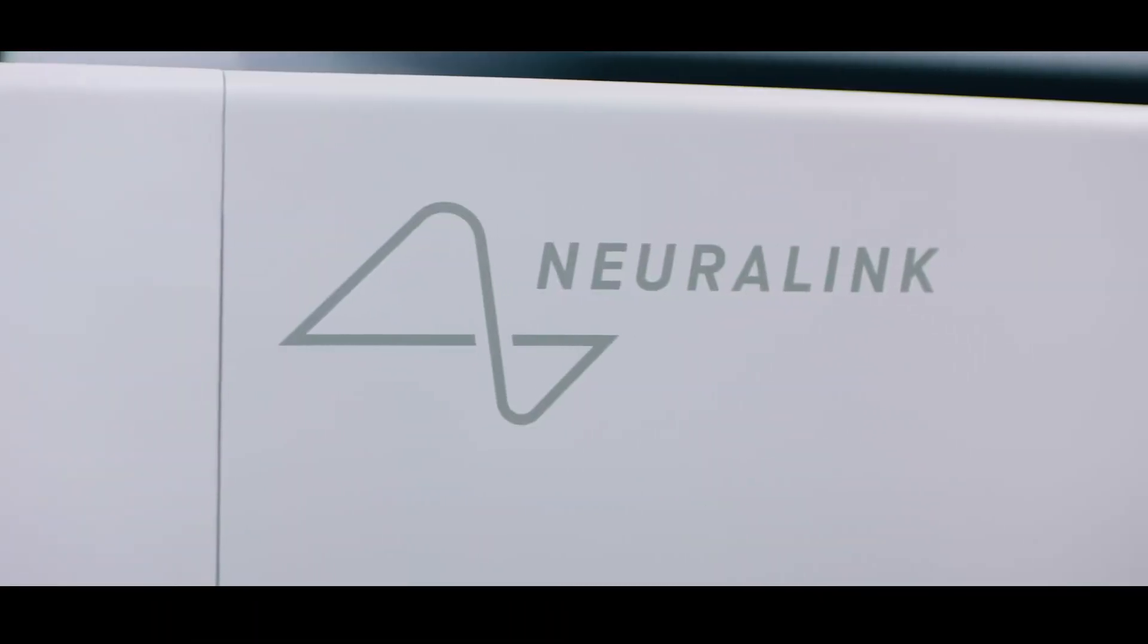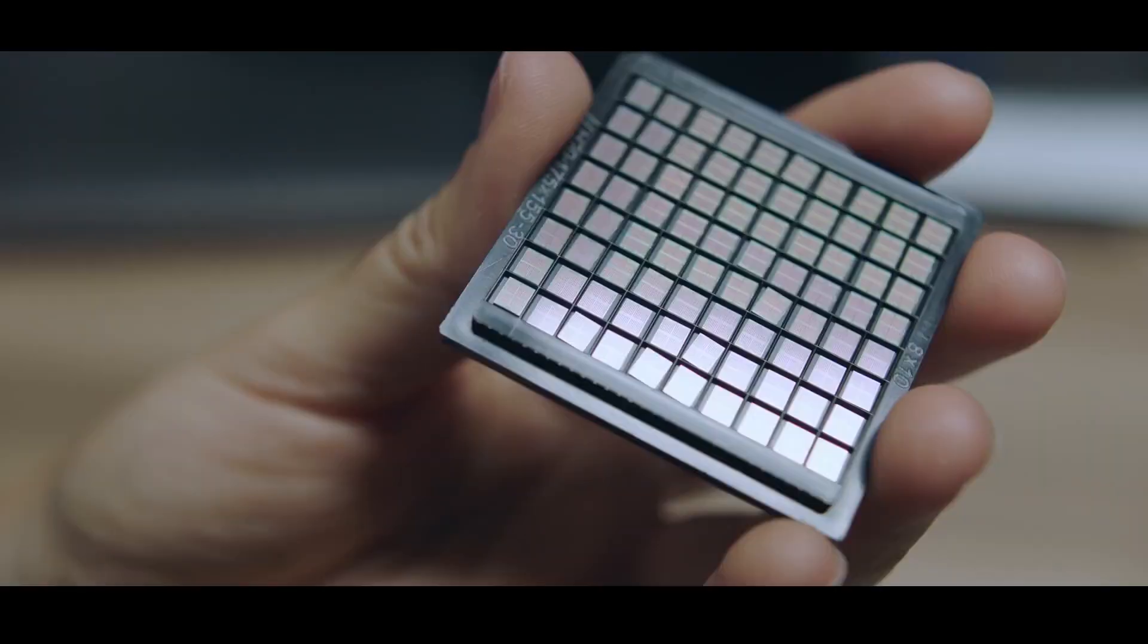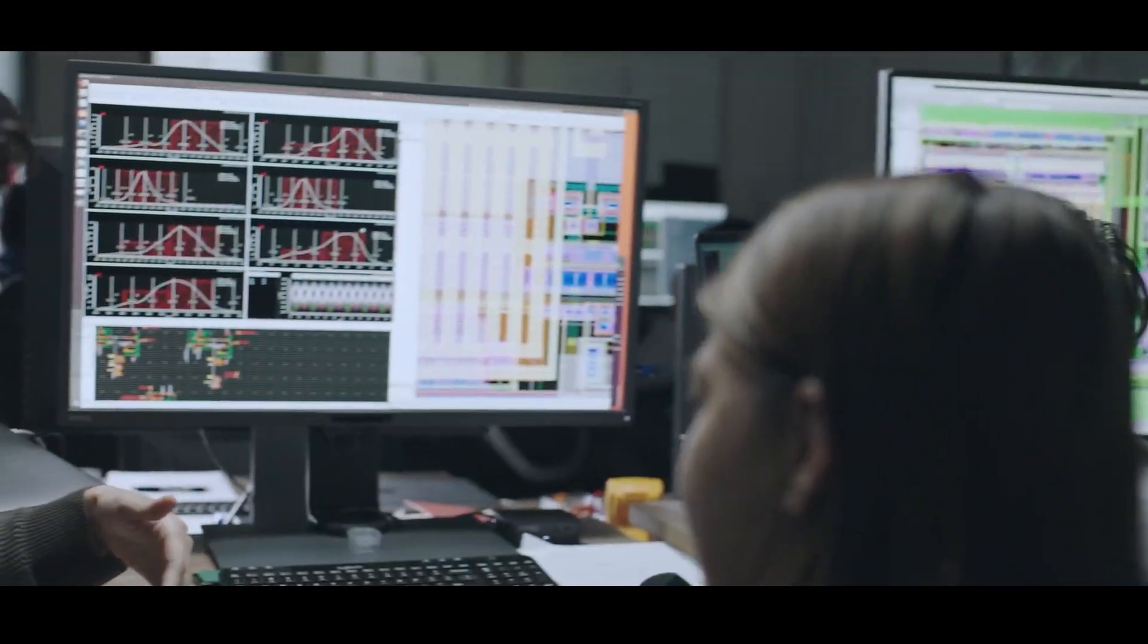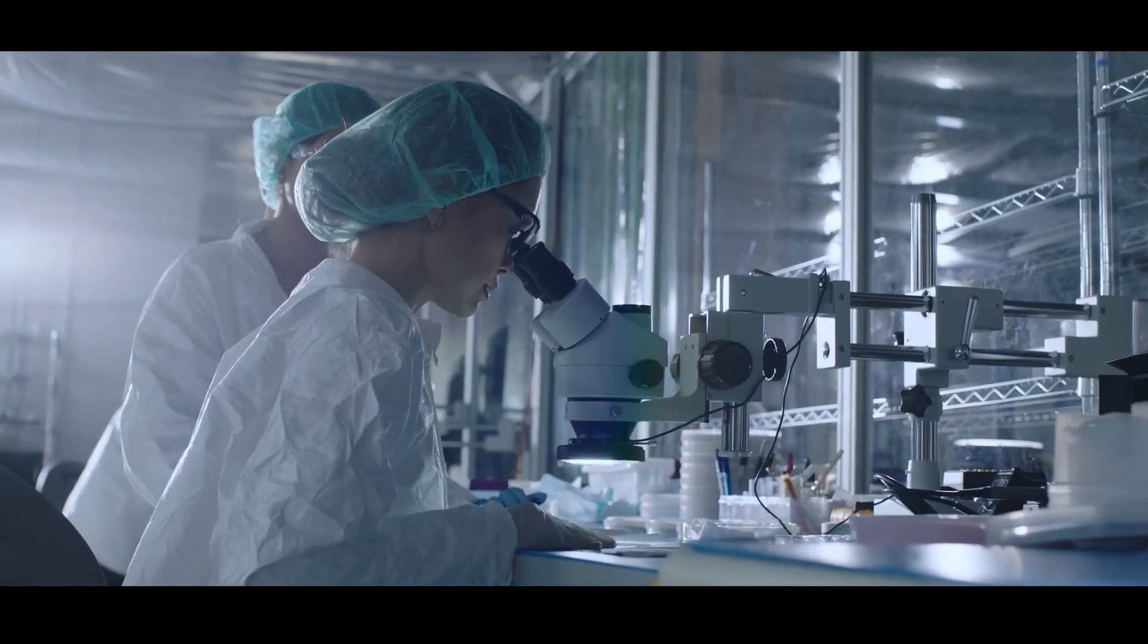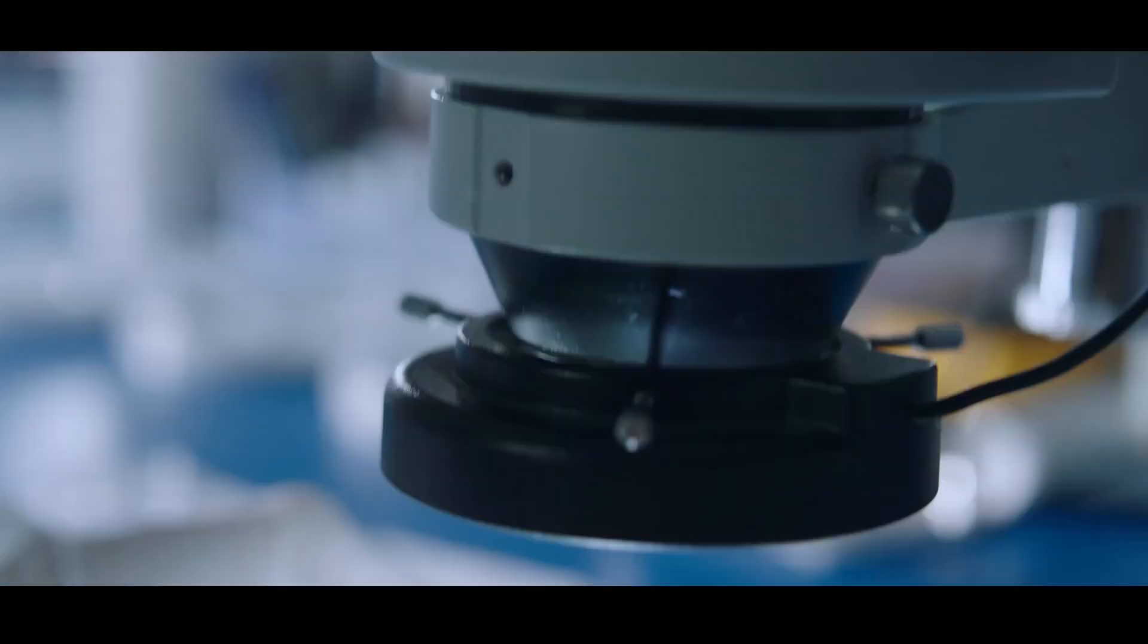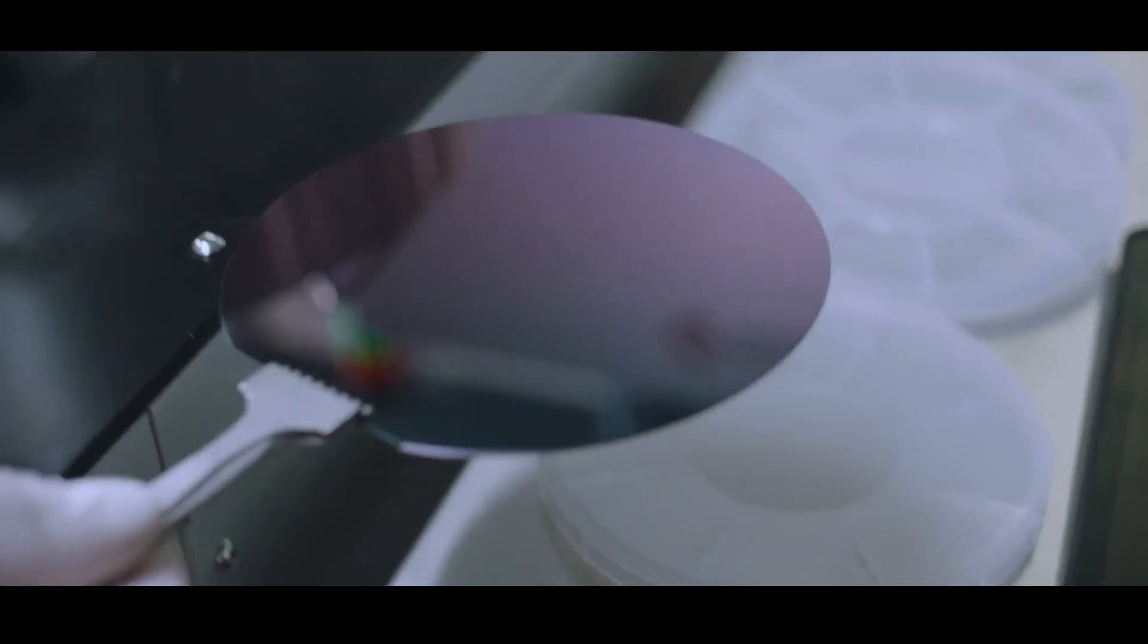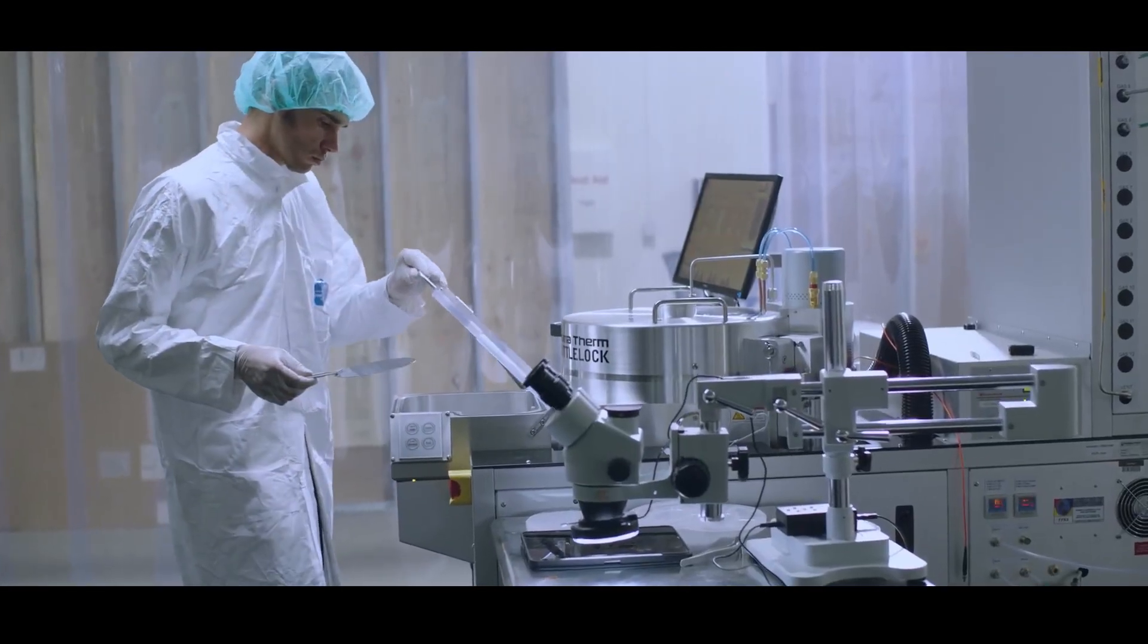Since Neuralink started the microfabrication process in 2021, the time it takes to make a new design of electrode threads has been cut in half. This means that they can iterate to a new design in just a few days. Neuralink has its own method for producing the needles that insert electrodes into the cortex, carrying the vertical integration theme further. They do this using laser milling, which is similar to a CNC mill but has sub-micron accuracy.